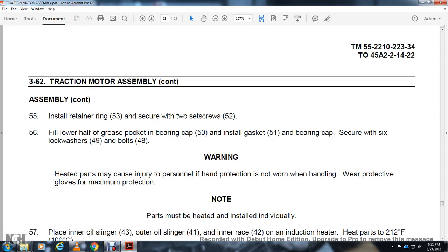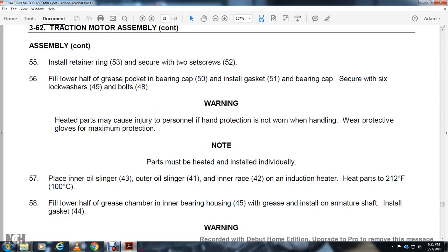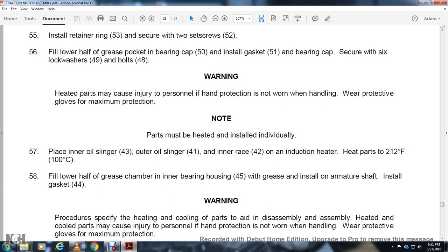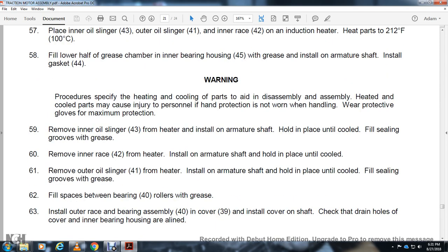Warning — heated parts may cause injury to personnel. Hand protection must be worn when handling; wear protective gloves for maximum protection. Parts must be heated and installed individually: place inner oil slinger 43 or outer oil slinger 41 and inner race 42 into induction heater. Heat parts to 212 degrees Fahrenheit. Fill half of the grease chamber in inner bearing housing 45 with grease. Install onto armature shaft and install gasket 44. Remove inner oil slinger 43 from heater and install on armature shaft. Hold in place until cooled. Fill seal groove with grease. Remove inner race from heater and install on armature shaft. Hold in place until cooled. Remove outer oil slinger 41 from heater and install on armature shaft. Hold in place until cooled. Fill sealing groove with grease. Fill space in bearings 40 with grease and install outer race bearing assembly 40 with cover 39. Install cover around the shaft and align the drain holes in the cover with inner bearing housing. Install two guide bolts into the inner bearing housing to aid in aligning the bearing housing, commutator, and cover.